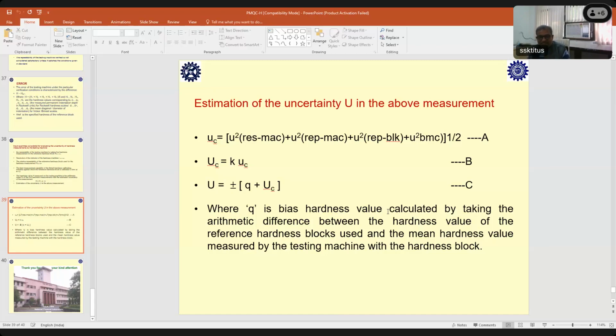I don't know the exact ASTM numbers, but I can get them for you. If people calibrate as per the ASTM standard, the only thing is that the requirement is a little less stringent, I would say, I mean the hardness tolerances. I forgot to mention that in this. So based on that standard we calibrate the blocks, and the standard machine is established as per that standard, and the testing machine and the general procedure, everything is based on the standard procedure. So it's a kind of process and procedure. It is not a unit.